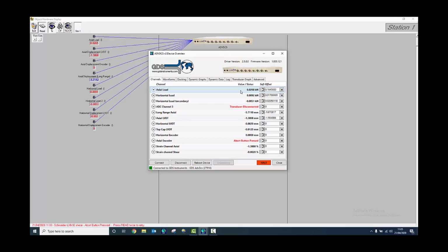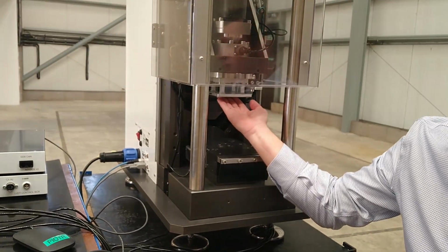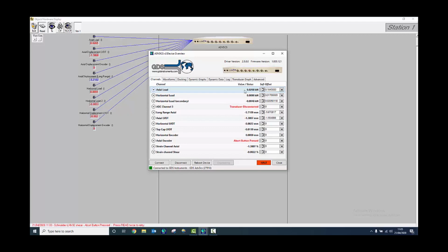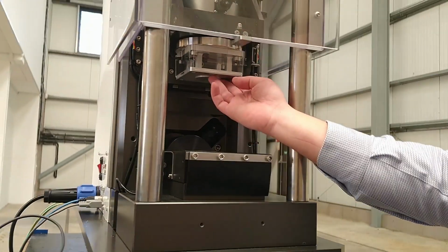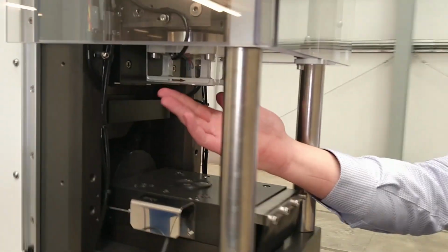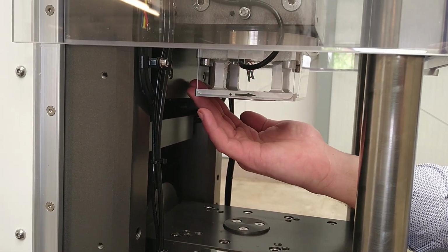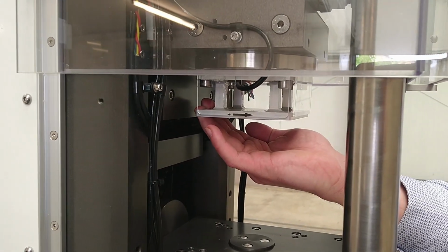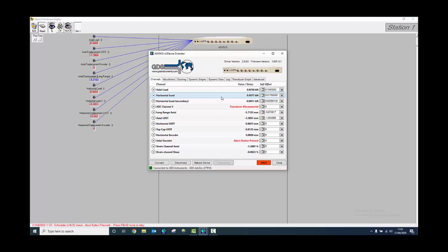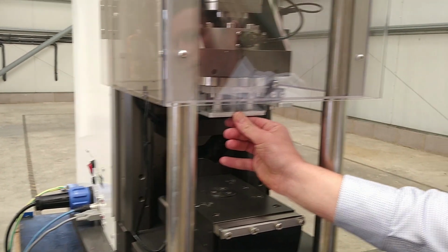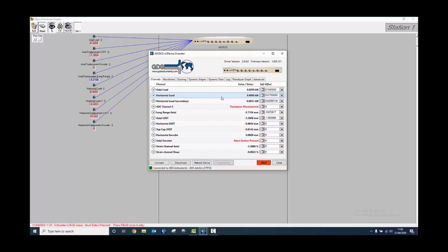Right. Go over here and try to push the carriage up with my hand. I should see a change in the axial load. And if I release it, the load should go back to 0. So we know that the axial load cell is working. So next one would be the horizontal load cell, which is the load cell over here or left. If you look to the side of the load cell, you'll see which way is the positive direction denoted with an arrow. So if I grab the back of the load cell and pull it towards the front of the machine, I should see the load changing to the positive value. And when I release it, it should go back to 0. If I push in front of the load cell, the load goes to negative. When I release it, it goes back to 0. So we know our second load cell is working.